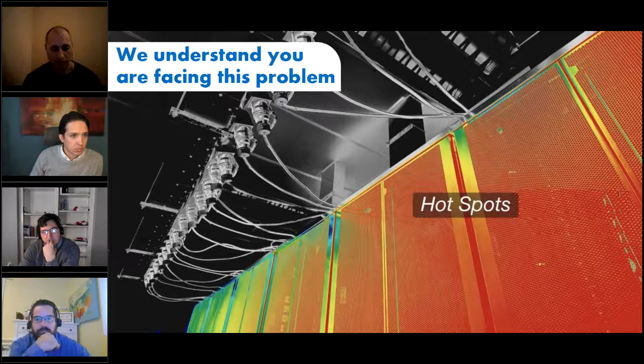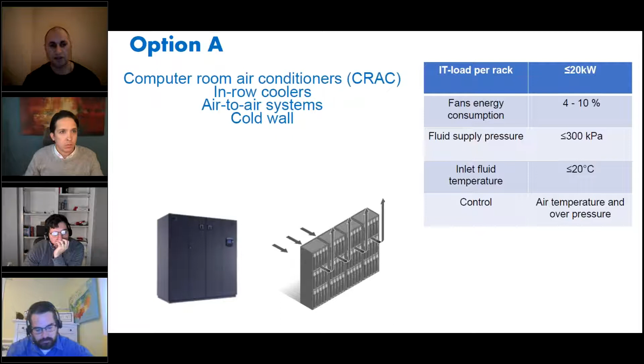In the classic version of data center cooling with CRAC, in-row, air-to-air systems or cold wall, in most cases the real power does not reach the calculated capacity, because cooling the air is not the same as cooling the servers. There is no guarantee from the cooling unit producer that everything will work as you wish, and the operational service of each data center is involved in an endless process of balancing airflows. And the server racks with powerful servers are half full or less, so the owner of the data center is losing money due to inefficient engineering infrastructure.